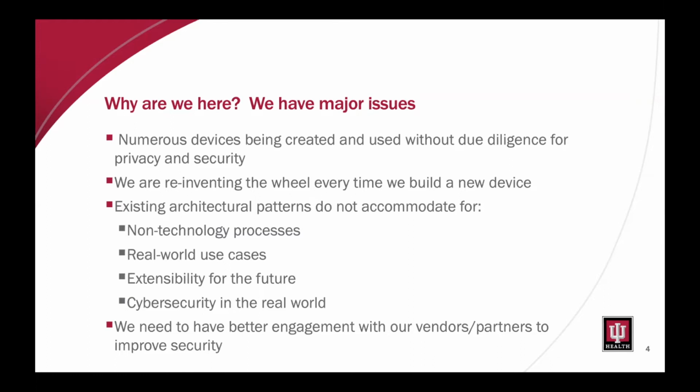And extensibility for the future is also a major concern, especially for a number of devices that have older operating systems, or more importantly, older forms of encryption, and also cybersecurity in the real world. So what I mean by that, and how this differs from real world use cases, is that cybersecurity in an actual hospital and the challenges we face there are a lot different than the tests that you have to do to be accredited by some standards body.